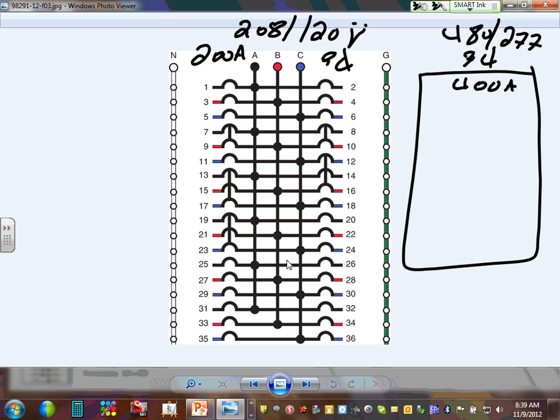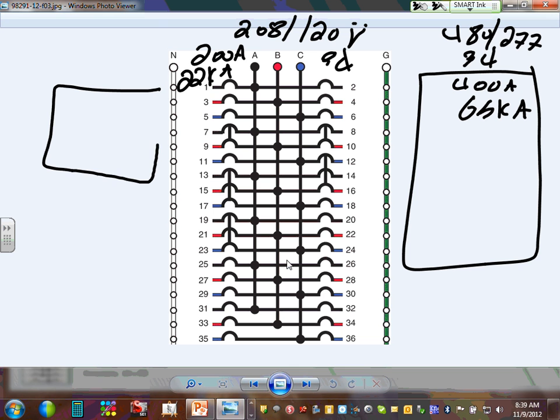By code, you have to put a label right at the top of the panel that identifies the voltage of the panel and the amp of the panel. You also have to have the interrupting rating. So 65 kilo amp. This one is 22 kilo amp. The last thing that you need to identify by code, which people don't understand, is the color code of the wiring system. So right here, you're going to do the following: phase A, phase B, phase C, color code for the wiring.